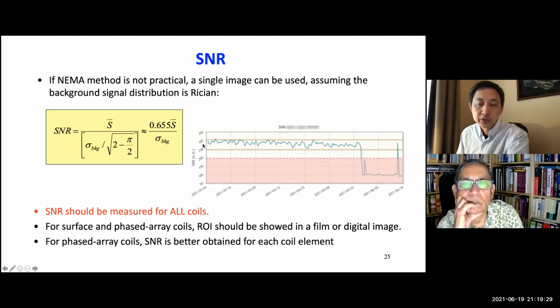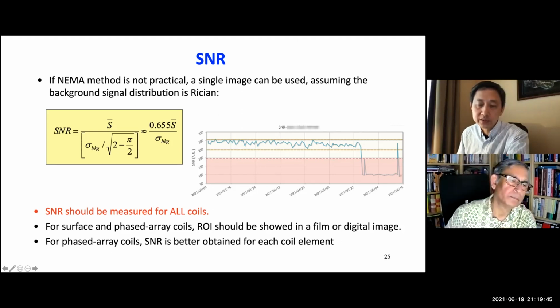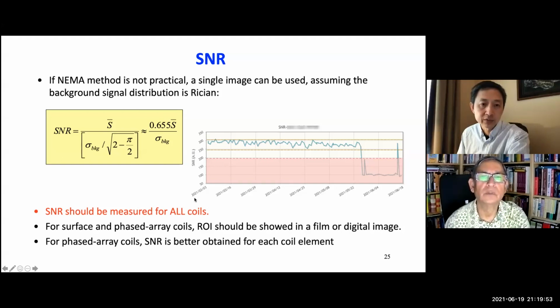Here shows you the daily SNR result, and at a certain point, it dropped quickly to a low SNR, and this was definitely caused by a bad coil. So we put the coil out of service and requested a replacement. The SNR should be measured for all coils. This is annual testing. Okay, annually, we need to measure all the coils.